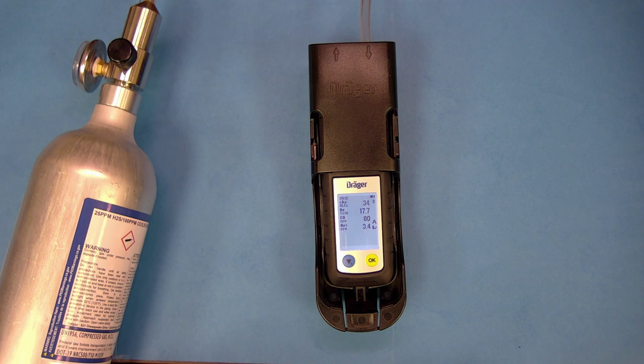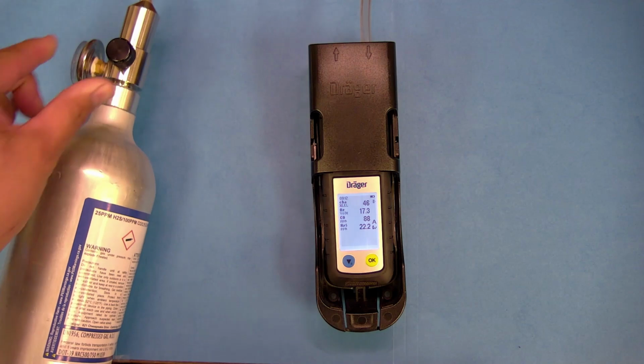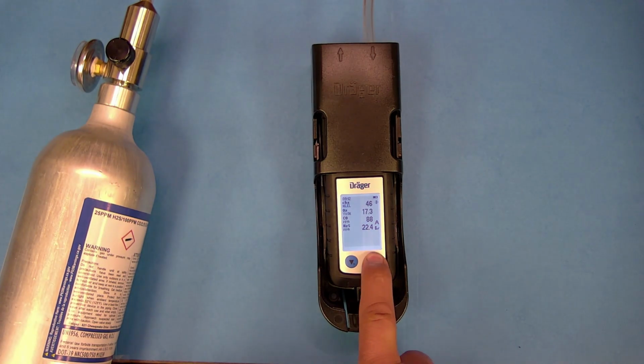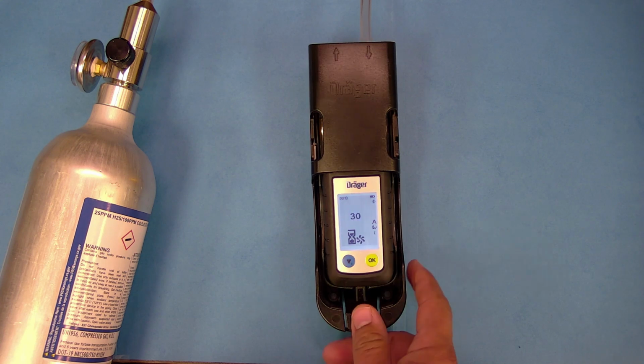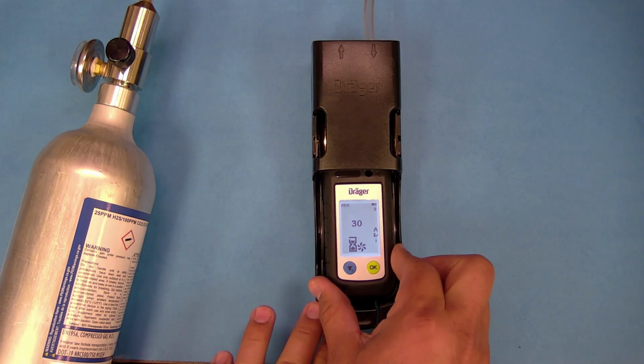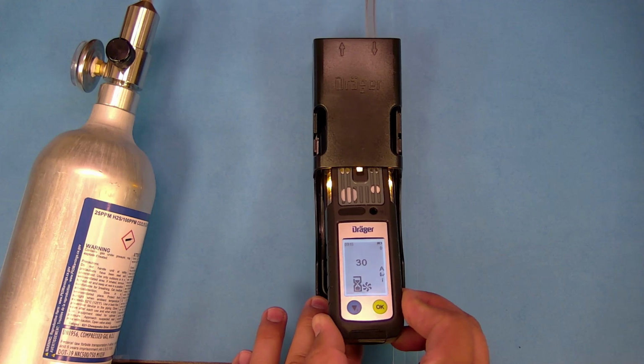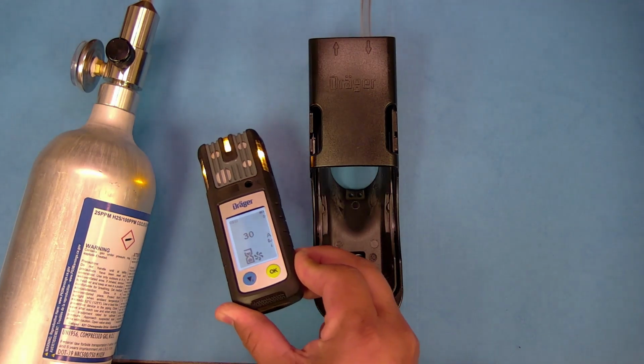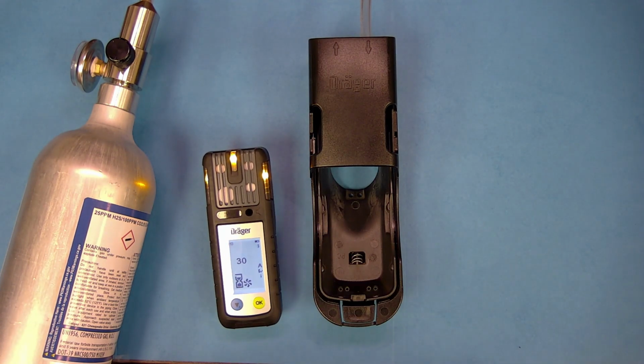The unit goes into alarm and you will get OKs next to each sensor. Once all 4 sensors have okayed, you can shut off the gas and hit OK on the monitor. You're going to hit OK one more time to save this bump test. You can push the eject button on the bottom of the cal adapter and take out the device. We have just completed a successful bump test through the quick menu.